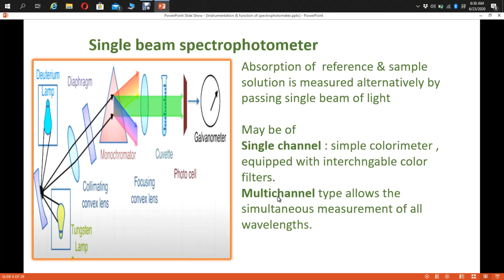Then after analysis of the reference solution, the sample solution will be put in the sample compartment, and the absorption is measured on the readout device. Now the single beam spectrophotometer may be a single channel or a multi-channel spectrophotometer. In single channel, it is a simple colorimeter equipped with interchangeable color filters, while the multi-channel type single beam UV visible spectrophotometer allows simultaneous measurement of all wavelengths. These are the two different types of single beam UV visible spectrophotometer.